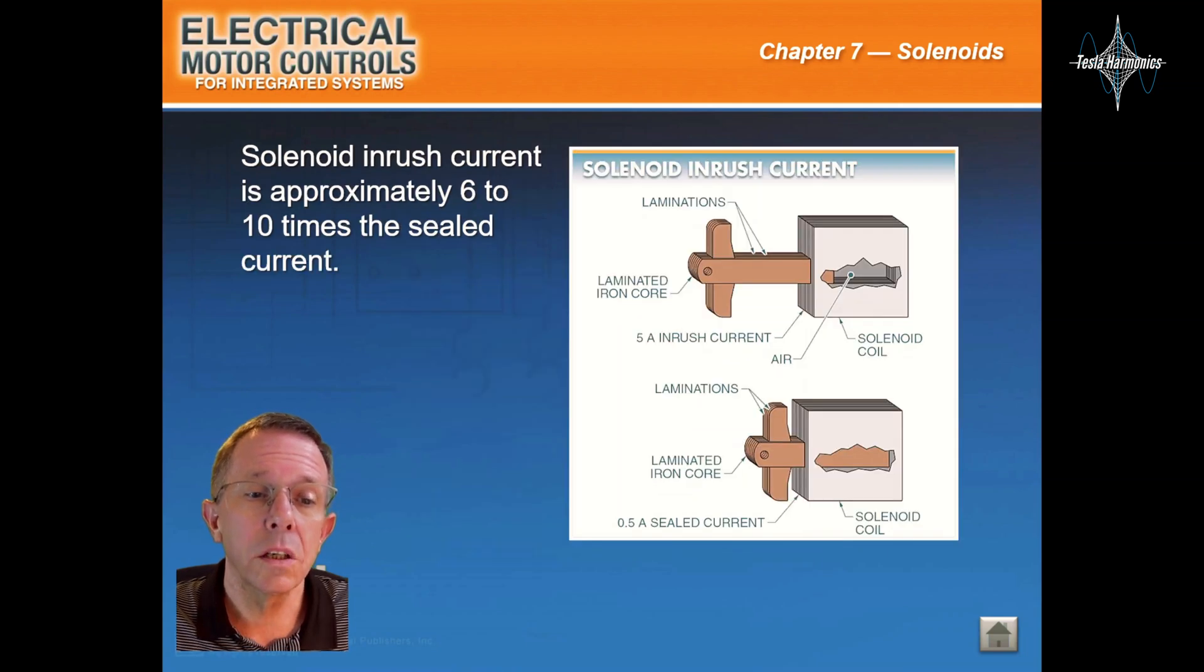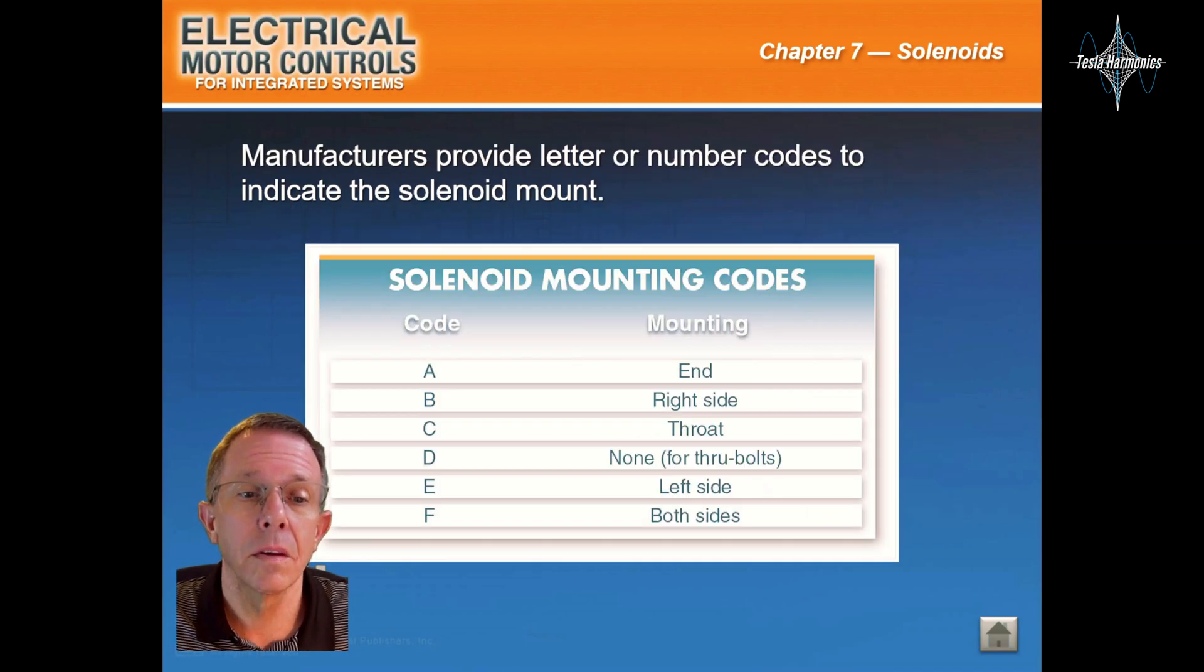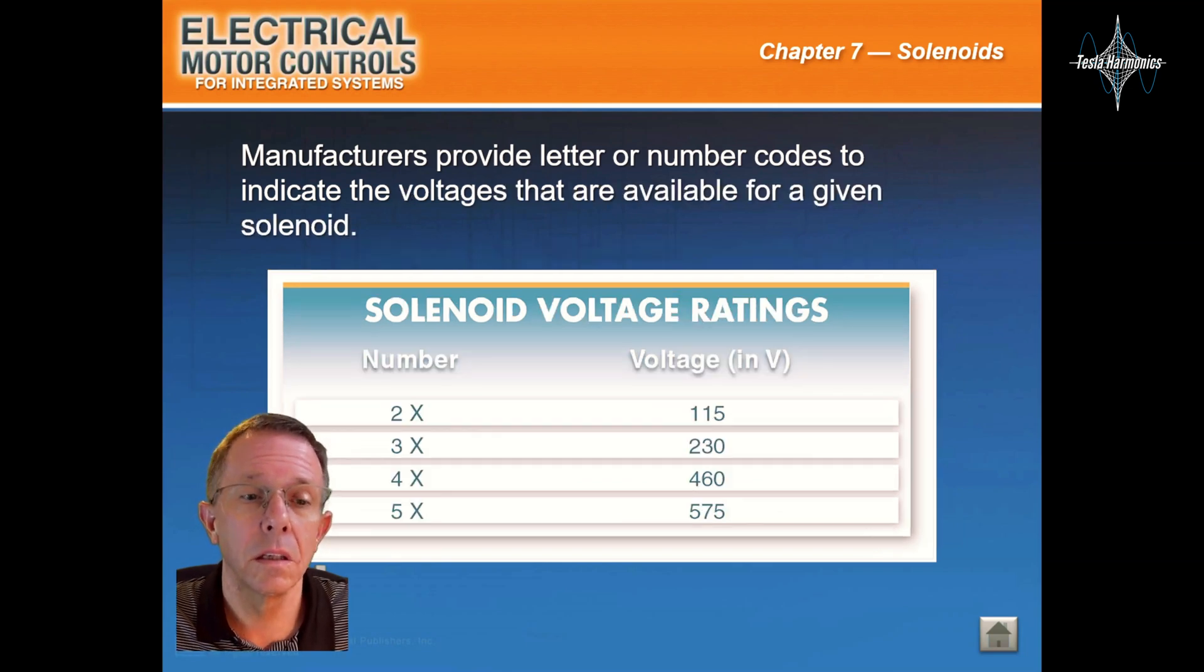The solenoid inrush current is approximately six to ten times the sealed current. Manufacturers provide letter or number codes to indicate the solenoid mount and the voltages that are available for a given solenoid.